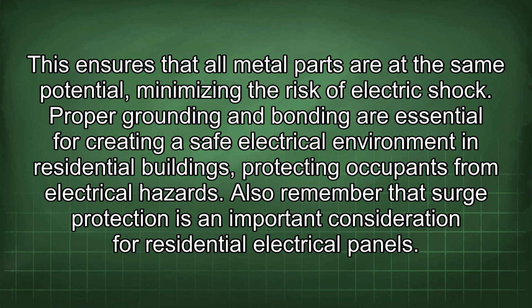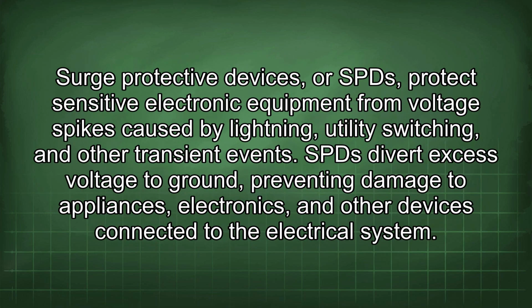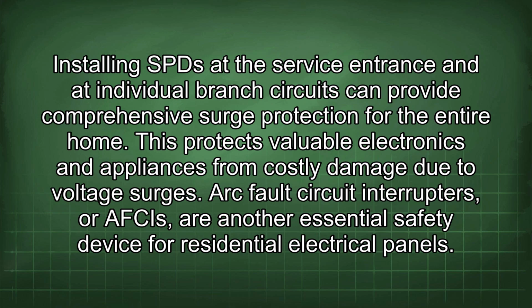Also remember that surge protection is an important consideration for residential electrical panels. Surge protective devices, or SPDs, protect sensitive electronic equipment from voltage spikes caused by lightning, utility switching, and other transient events. SPDs divert excess voltage to ground, preventing damage to appliances, electronics, and other devices connected to the electrical system. Installing SPDs at the service entrance and at individual branch circuits can provide comprehensive surge protection for the entire home. This protects valuable electronics and appliances from costly damage due to voltage surges.